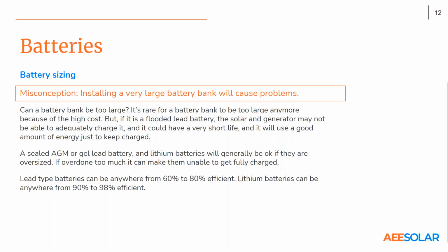There we go. Installing a very large battery bank will cause problems. Well, if it's large enough, yes. And it also depends on what kind of battery it is. It's rare for a battery bank to be too large because they cost so much now. It's not very often that I run into somebody that puts in a battery bank that's too large. But if it's a flooded lead battery, they do require a certain amount of push current pumped into them to really operate well. And if you don't have enough solar, or a large enough generator to adequately charge it, it will not get fully charged, and then it will sulfate, and it will reduce its life pretty substantially.